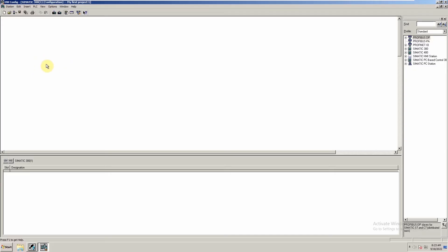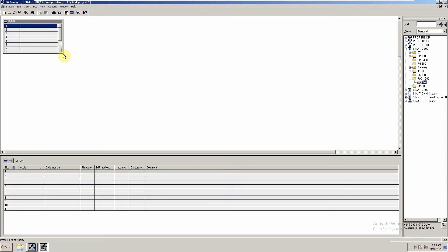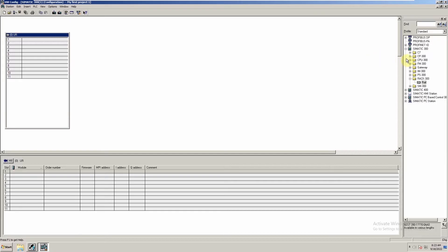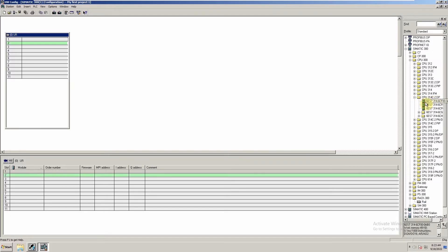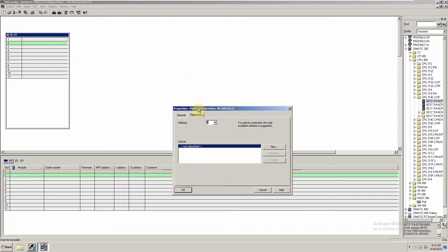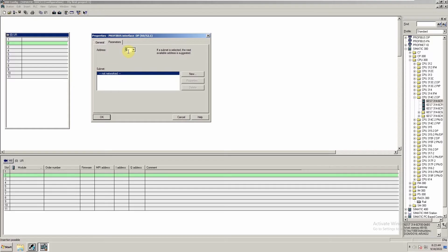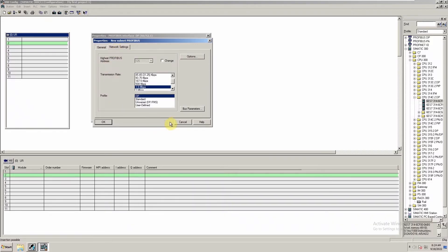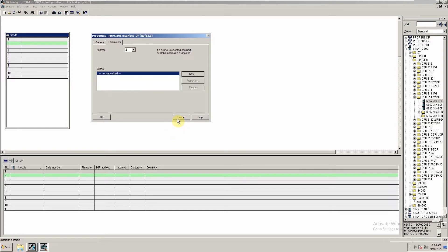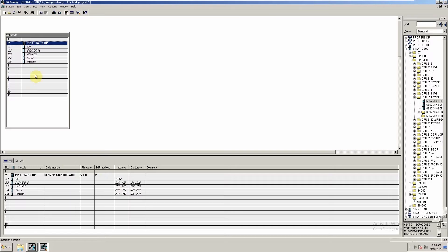In the hardware configuration, we can add CPUs, I/O modules, and configure communication like PROFIBUS or MPI for the CPU. First, we will go to SIMATIC S7-300, open Rack-300, and double click on the rail — this will add a rail to the project. Next, we want to add our CPU. Today we will add a CPU 314C-2DP. We drag and drop this CPU onto the rail. A menu opens where we can select the PROFIBUS address and configure PROFIBUS communication options and network settings. Today we will not use these options, so we click OK. Our CPU is now added to the project.